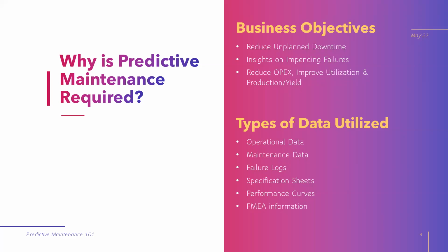Then talking about failures, there's a different time period needed to intervene and check for a particular failure event. Some failure events can simply be intervened with a kind of cleaning. For example, if there's fouling happening in a heat exchanger, a methanol cleaning can solve the problem, taking about a day or two. But if you're talking about burning of valves, since equipment like compressors are being pushed beyond their limits, that might take days to weeks to get corrected and bring back to normal operational state.